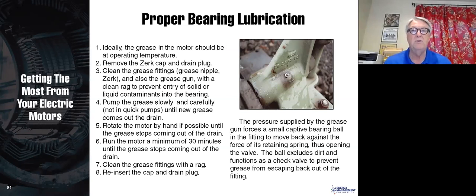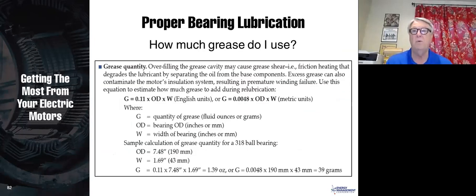So you wait till the new grease comes out of the drain, then you rotate the motor by hand if possible, and wait until grease stops coming out of the drain. Don't put the drain plug on right away. I'll show you why in a moment. Run the motor for a minimum of 30 minutes until the grease stops coming out of the drain. Then go ahead and clean those grease fittings, reinsert the cap and the drain plug. This is a little more difficult than the way a lot of people grease the motor, but if you want it to last a long time, you'll want to use that.